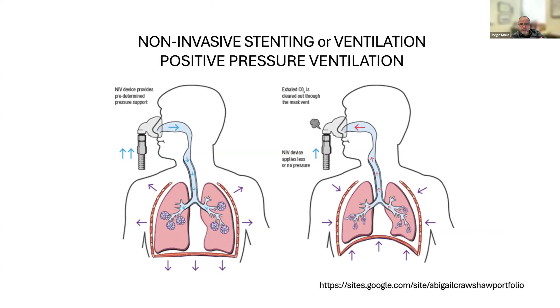This makes measurements and steady ventilation more complex and requires that algorithms within the devices are able to analyze this. On the other hand, this particular need has also led devices to manage leak very well, as happens in home mechanical ventilators, which is not true for invasive ventilators typically used in the ICU. If you have a leak, you probably know that these ventilators go absolutely insane. That is not true for ventilators designed for non-invasive ventilation.